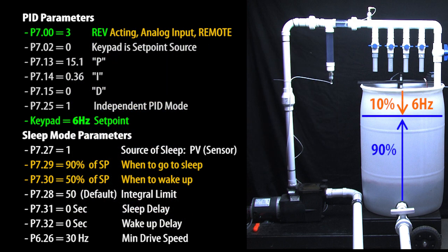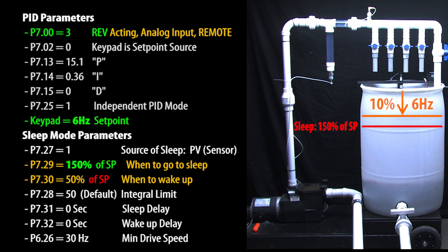We also need to change our wake and sleep set points to match the reverse acting sensor. In the previous video we found the sleep and wake levels are relative to the set point. So, since the set point is at 10% and suppose I want to shut the motor down at another 50% of that, then my sleep level is 150% of the set point, which would be 9 Hz.